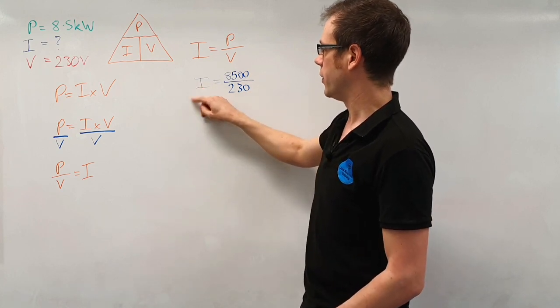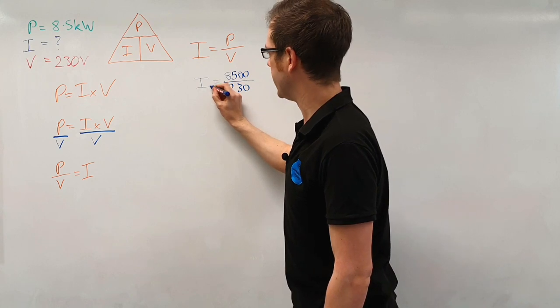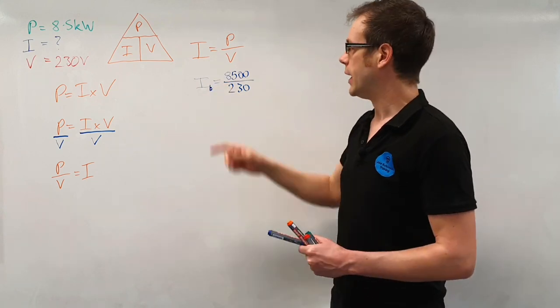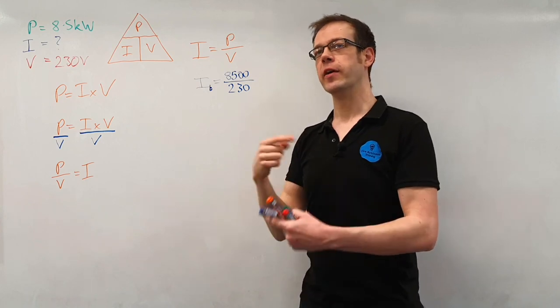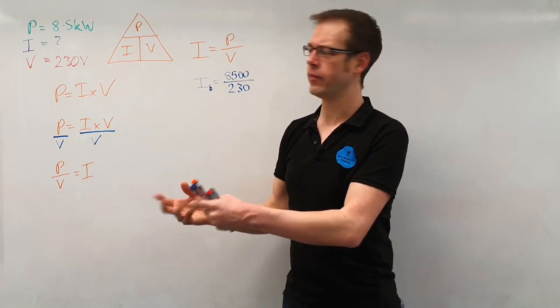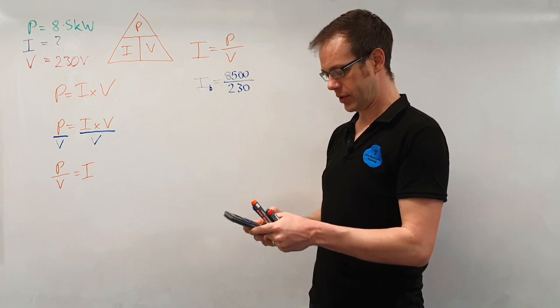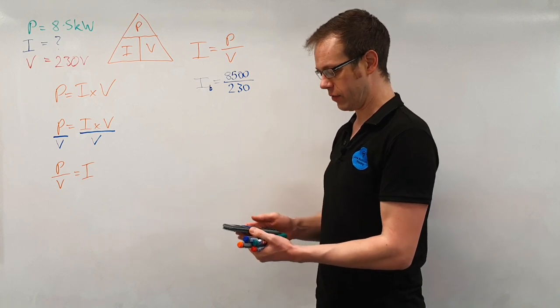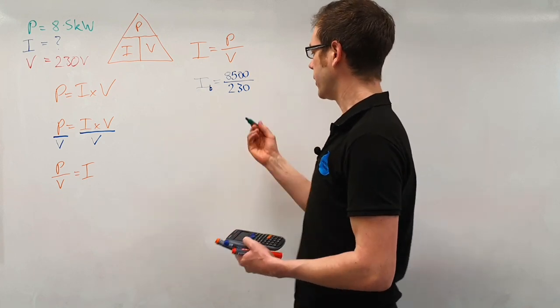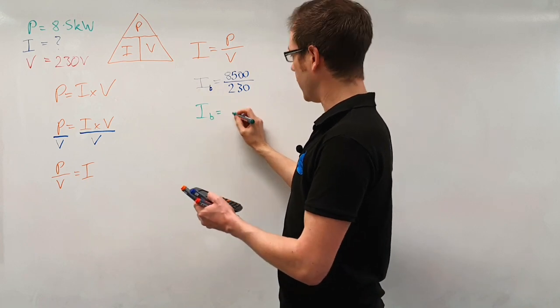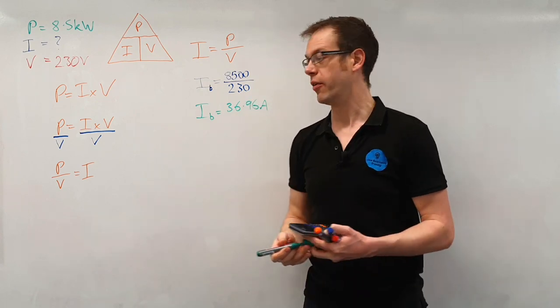So there's our power, there's our voltage and that's going to give us our current. Just a little word on this, if you are doing this for design work what you'll find is that this will actually be called IB with a little b in the subscript. IB is equal to 8500 divided by 230 and that just means design current. So let's do that calculation, 8500 divided by 230 and that gives us a value of 36.96. So we've got 36.96 amps. The current that our shower is going to draw according to our design calculation will be 36.96 amperes, that's how much current that circuit is going to draw.